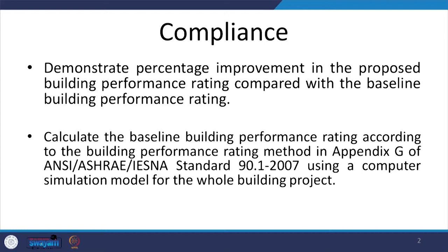So, when we are talking about the compliance as per whole building performance method, we have already seen that we have to demonstrate through simulation that either the energy consumption of the proposed case is less than that of the base case, as calculated through the calculation of EPI, energy performance index, which is a normalized rate of energy consumption, or we calculate that the number of unmet hours of thermal comfort of the proposed case is less than that of the base case. So, either of the two ways will be used for demonstrating the compliance depending upon whether the building is an air conditioned building or a naturally ventilated building.